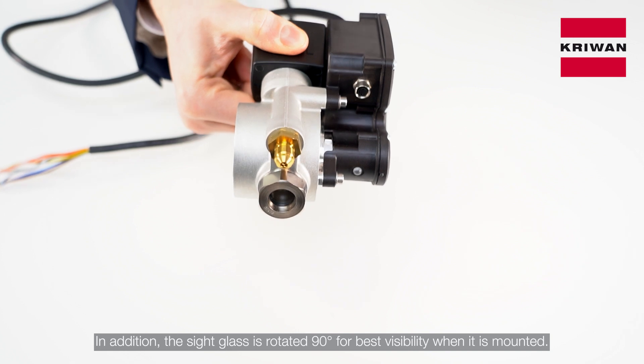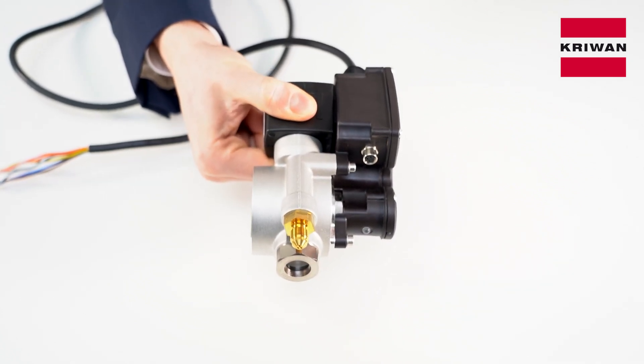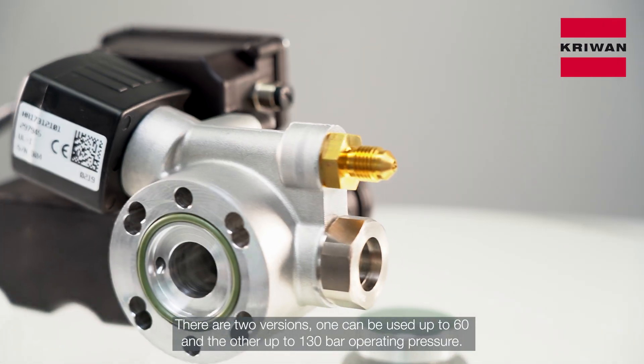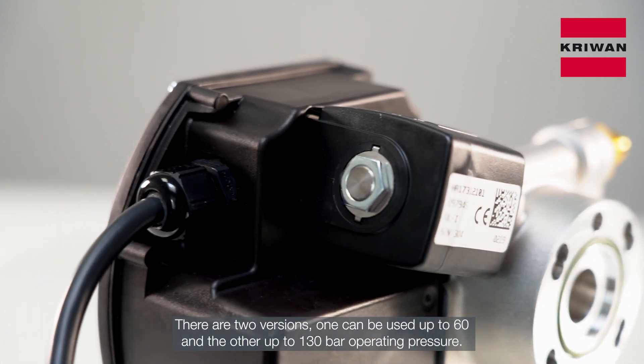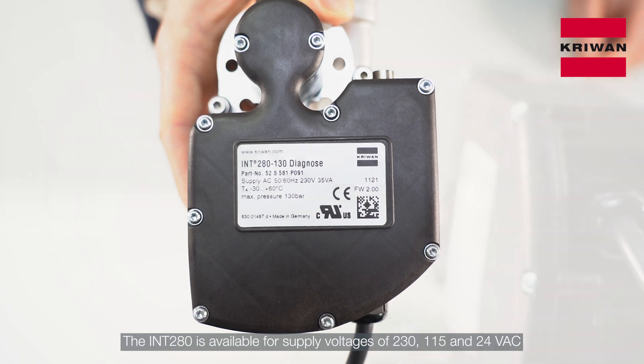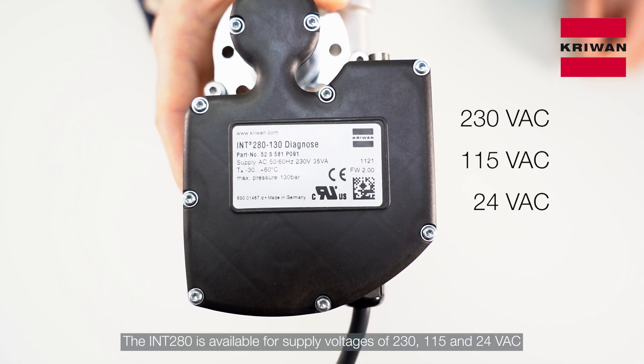the INT280 can be mounted in two directions. In addition, the sight glass is rotated 90 degrees for best visibility when it is mounted. There are two versions — one can be used up to 60 bar and the other up to 130 bar operating pressure. The INT280 is available for supply voltages of 230, 115 and 24 volts AC.